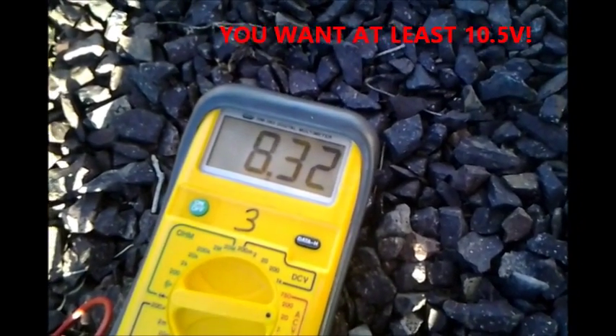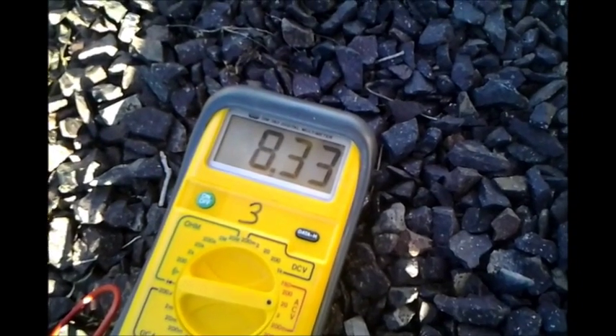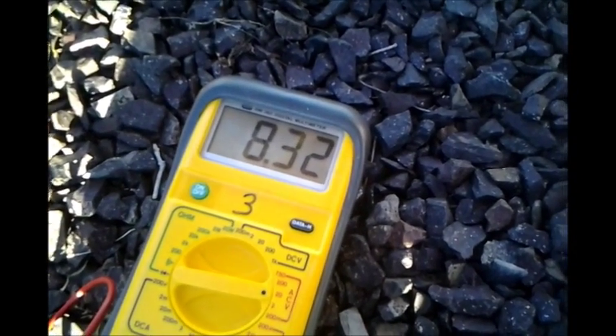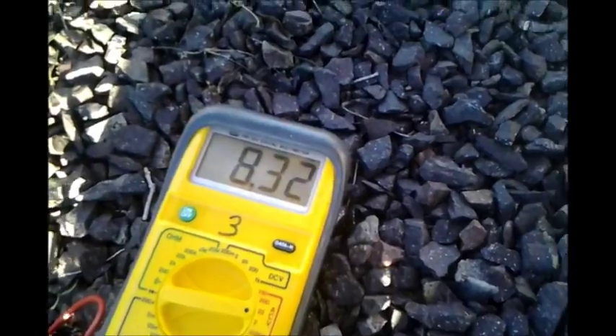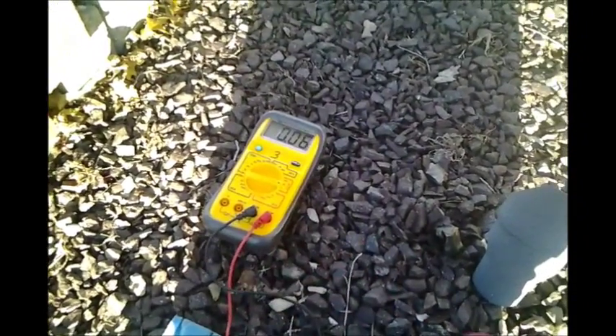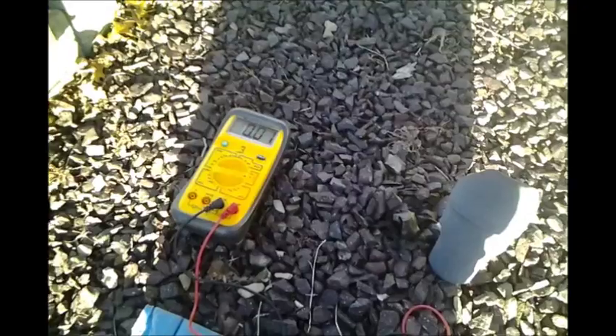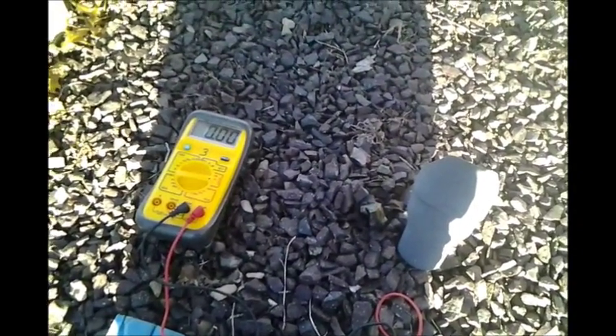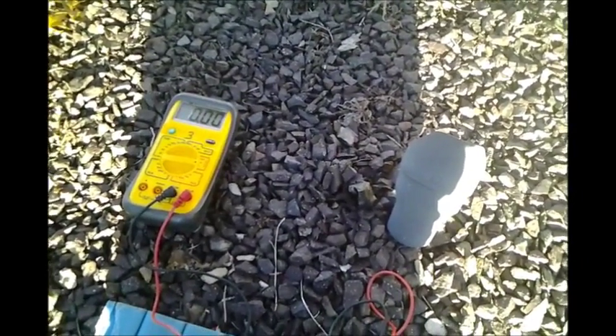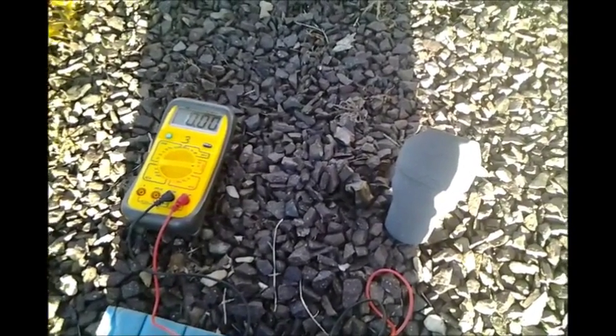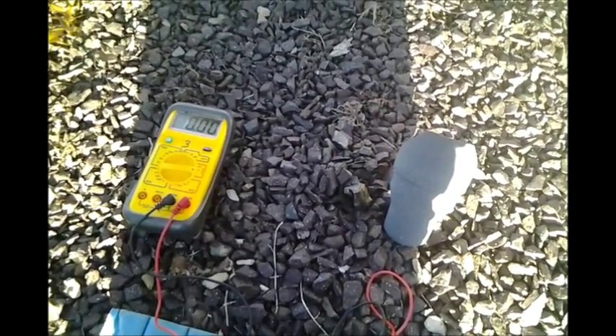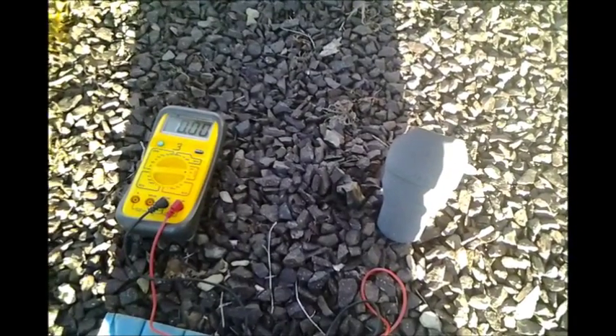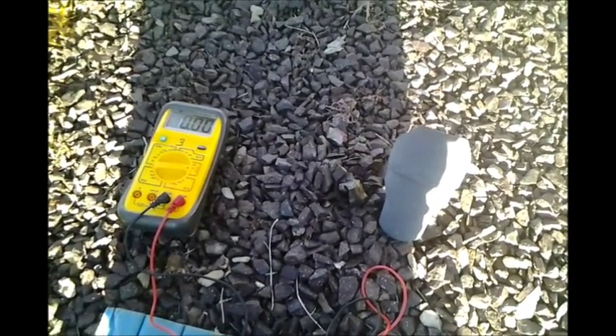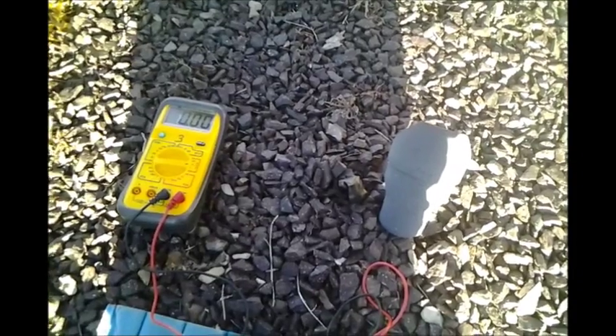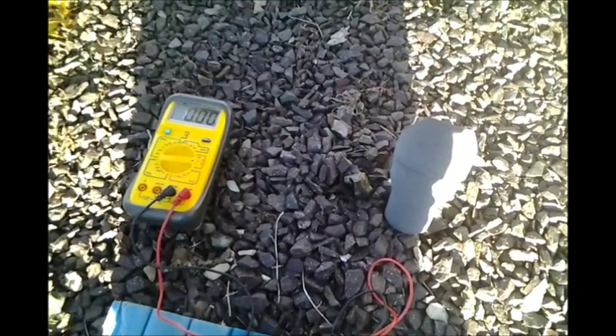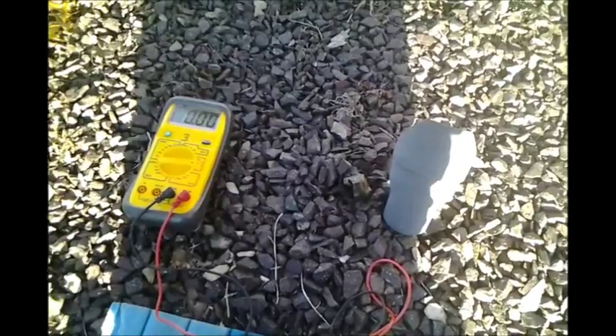So I need to do something to increase the voltage on this end and decrease it on the other end. I'm considering taking one of the 6 lights on this end and wiring it into the other end, and then supplementing the number 14 wire on the short run with a long piece of number 16, to see if I can get enough voltage drop to stop burning out that bulb.